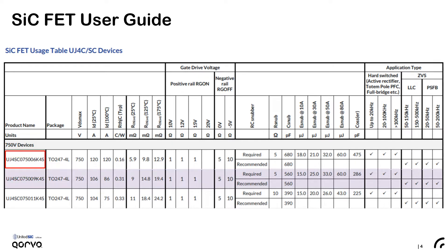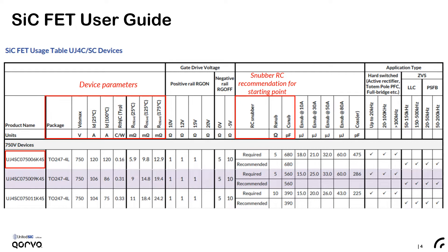The first column gives the device part number. This group of columns gives device parameters. The gate drive voltage group gives gate resistor recommendations for different gate drive voltage levels. This group of columns gives snubber recommendations as a starting point, and right next to it is the snubber resistor loss at different current levels. The application types will have an impact on our snubber recommendations — as required, recommended, optional, or no need.